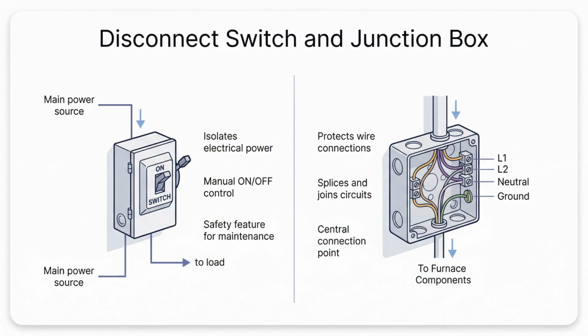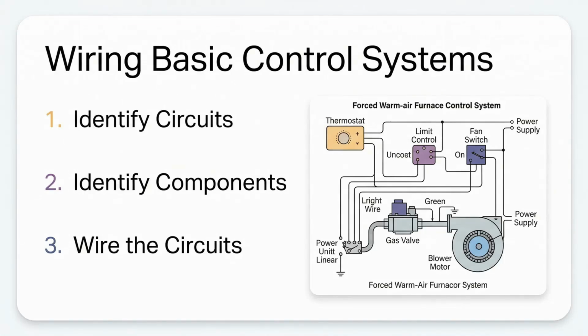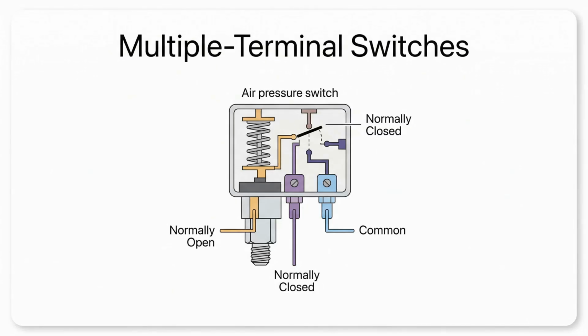Once power reaches the appliance, all 110-volt connections must be made inside a metal junction box to prevent short circuits and shock hazards. When you open an appliance and see a plate of spaghetti wiring, do not panic. Follow a systematic approach. First, identify the four main circuits: combustion safety, control, transformer, and fan. Second, locate the switches and loads for each. Finally, wire them one by one, starting with the highest voltage, like the 110-volt fan circuit, and working down to the millivoltage safety circuits.